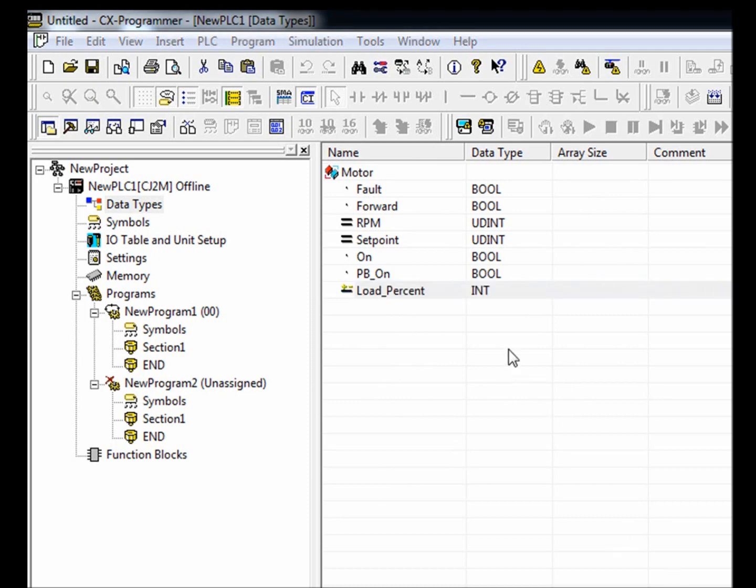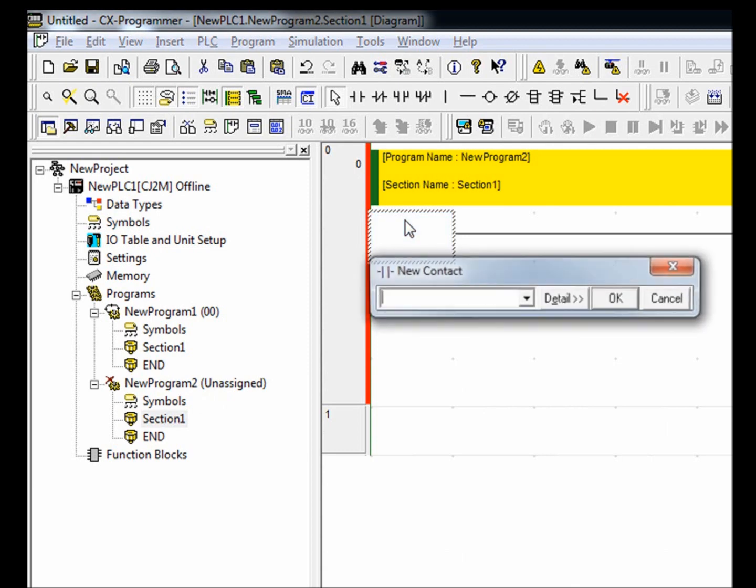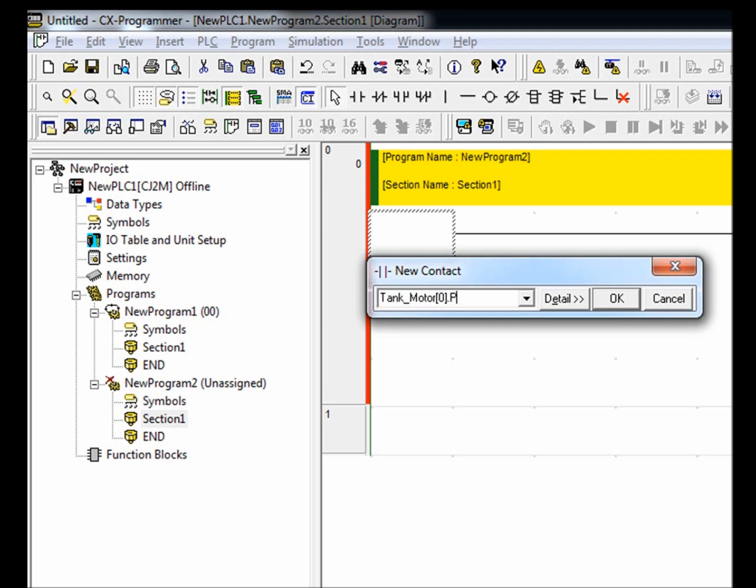Now I'm going to show you how to use your new data structure in ladder. I'm going to insert a new contact here. To assign a member to this contact, simply type in the symbol name, which was tank motor, open bracket, an array index, which I'm going to choose zero, close bracket, dot, and then the member name, which I'm going to use push button on.